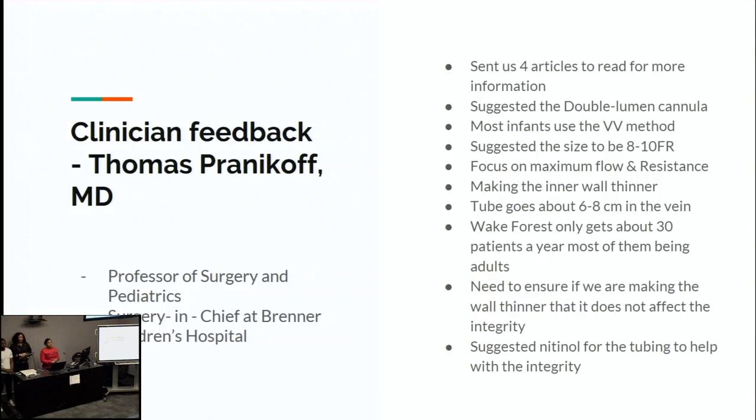Our first meeting was with Dr. Pranikoff, a professor of surgery and pediatrics, and the surgeon-in-chief at Brenner Children's Hospital at Wake Forest. He sent us 4 articles to read, most of them from the University of Michigan, because that's where the whole ECMO design came about and was started. He suggested that we do a double lumen cannula. Most infants use the VV method, the venovenous method, which goes through the vein. He suggested the size be 8 to 10 French, and to focus on maximum flow and resistance, making the inner wall thinner.